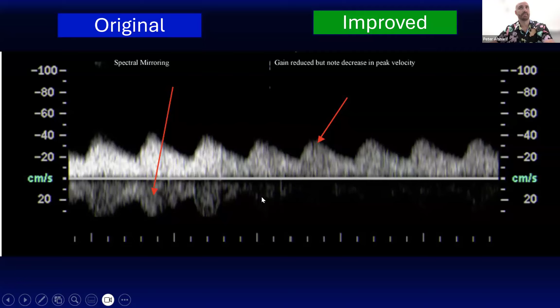And the importance of this is, why can't I just ignore this thing and just measure it here? But this is an indicator that your gain's too high. And by appropriately reducing the gain, you get a more accurate representation of what the flow is in the real direction. Is that clear? So just reduce the gain a bit if you see this phenomenon.